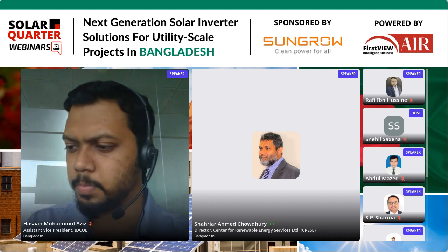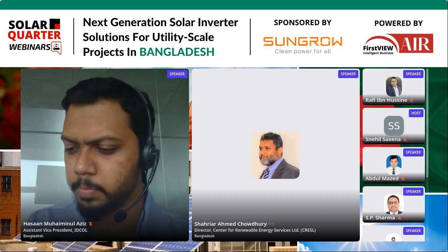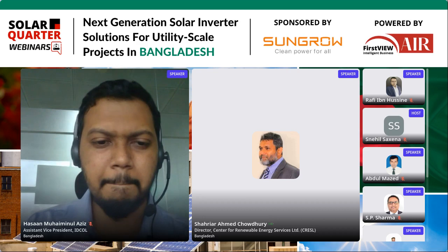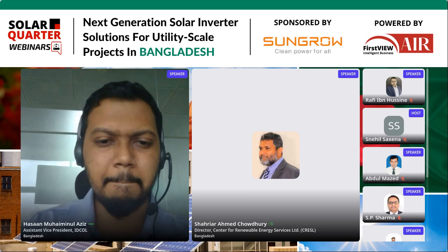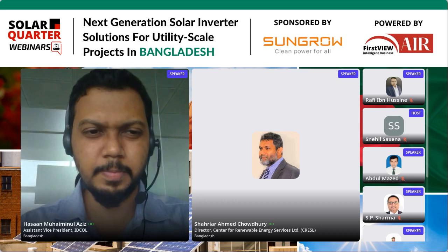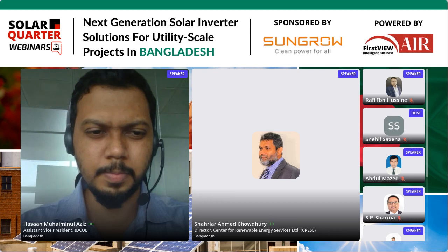These are the things we need to be very careful about while choosing the system. From my experience, I have seen a developer choose an inverter which had magnetic switching instead of solid state switching. On some days, due to variation of the voltage and frequency, one inverter may switch more than 50 or 60 times a day, and we found they had to change almost half of their inverters due to failure of the switching devices.